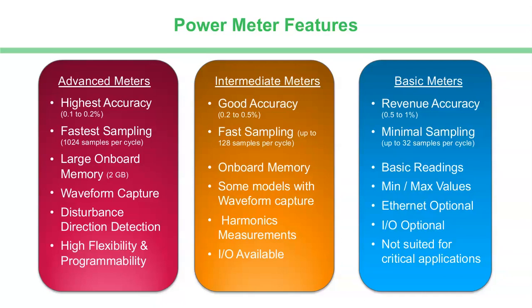In addition, you also start looking at the architecture of the metering and the network and the software, and you start looking at how data is managed. And the thing called onboard memory and the ability for the meter to capture data, to store it, and then to transfer it to a host becomes very important. So the advanced meters tend to have a large amount of memory, not only for data logging, but also for disturbance, waveform captures, and things like that. As you get into the intermediate and the basic, you tend to either not have onboard logging or have substantially less memory for that onboard logging.